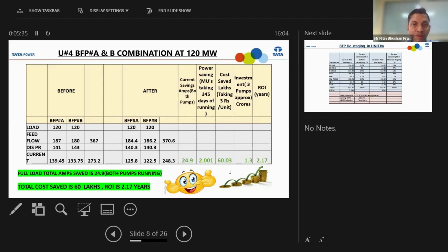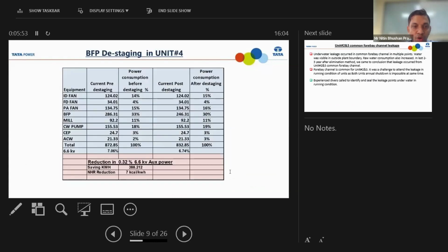auxiliary power saving initiative that we have done, and the same thing is implemented in Unit 4, post in Unit 3 and Unit 2. In 3 units we are saving, and you can say around 1.5 crore saving per year is there with this boiler de-staging. Total auxiliary power reduction is of 0.3% if we are talking about 6.6 kV, and the net heat rate reduction is around 7 kcal.